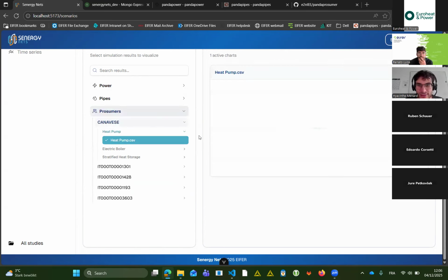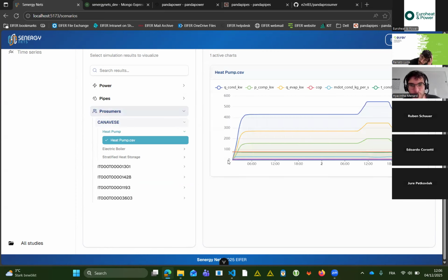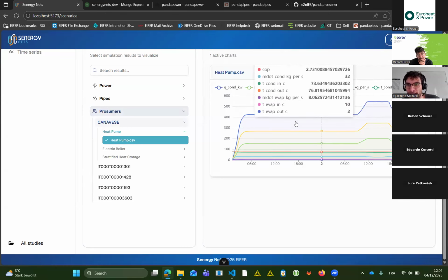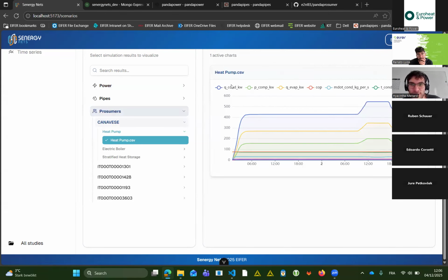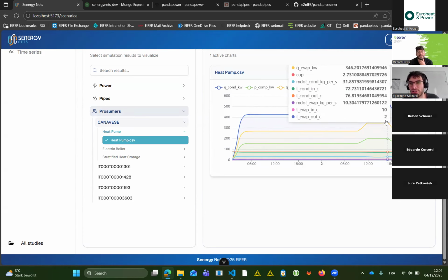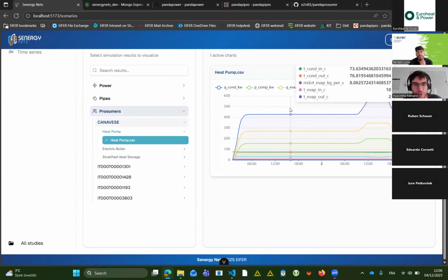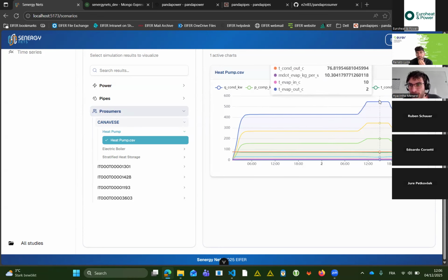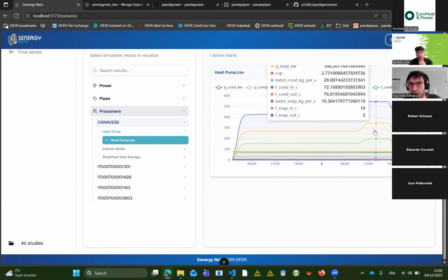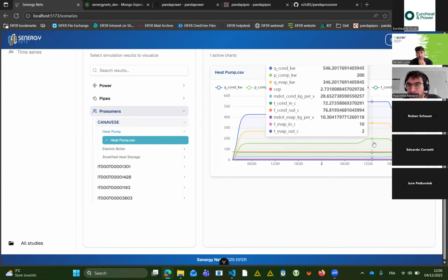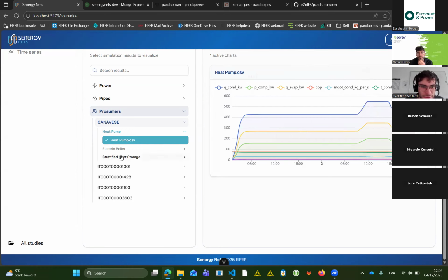And for the heat pump, I can see its profile, so I see all the results of the model. You can see, for example, in blue is the power of the condenser that is sent directly to the network. At this point, during my heat load, it will actually reach the 200 kilowatt maximum power, shown in green. So during this time, the heat pump will not be enough to cover the demand.